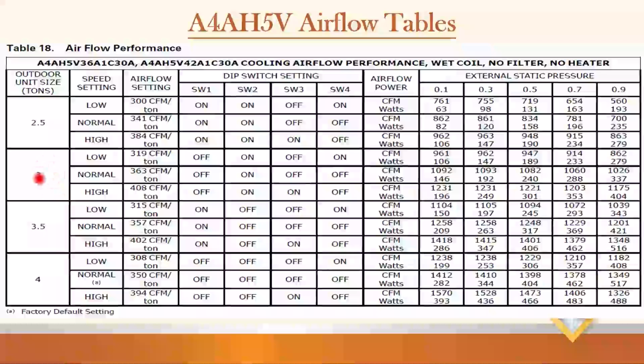Here's our setting. So if we're at a 3-ton, our normal's 363 CFM per ton. Here's our high at 408. Let's say high, 408 CFM per ton. We want dip switch 1 off, 2 on, 3 on, 4 off. And with our perfect static pressure at 0.5, we will be at 1221 CFM, 1082 on normal setting. So keep that in mind. Again, this is taking out all the guesswork. As long as you can get that static pressure, you can dial in that fan speed and prove that the system has enough air. If we're off that chart, this one goes up to 0.9.